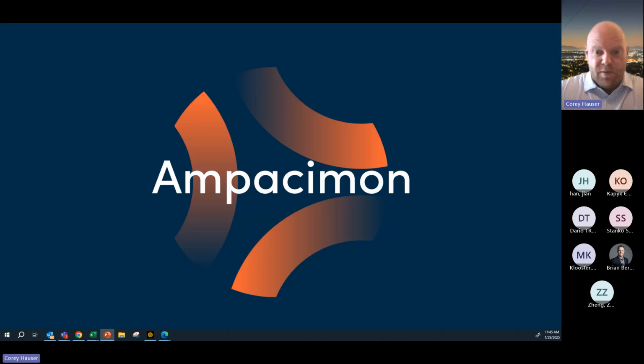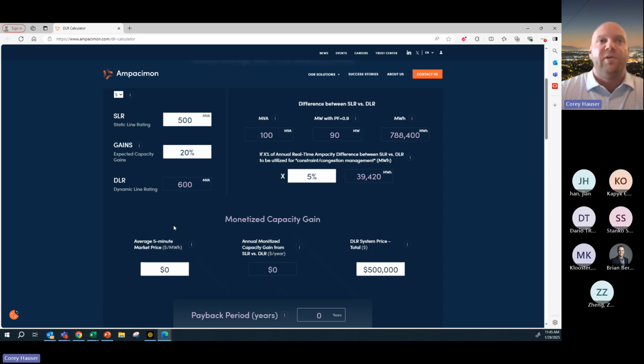All right. Now we just wanted to jump into one more thing, and I know it was the last one that we had on our list. Once we've completed an ADR view study where we get some information from you, whether it's some conductor information, some rating information, a KML file of your line, we're able to build a model of it in our back end and run a simulation that allows us, with an output of giving us the number of sensors, the placement of sensors, to produce a budgetary quote for you. But in this example here, the biggest thing that it does is it applies a year's worth of past weather data, and it provides what your dynamic line rating gains would have been versus your assumed ratings over that period of time.